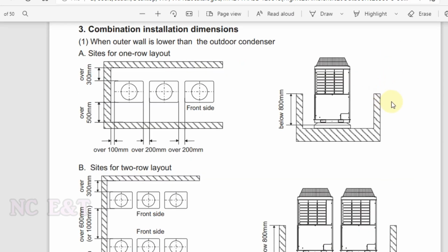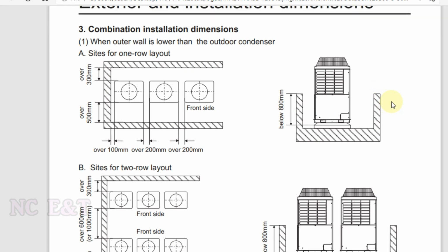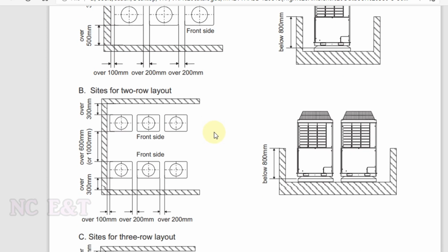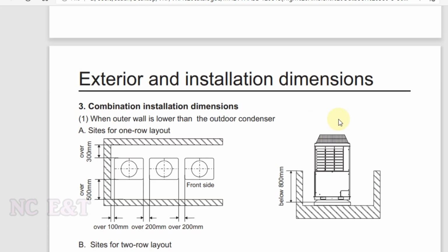There are some important points to be considered during the installation. If the location for the outdoor unit is covered by a boundary, then we must have a minimum clearance of 30 centimeter between the unit and the boundary wall. And if we have two rows of outdoor units, there must be a clearance of 60 centimeter between the two units. And the height of the boundary wall should not be more than 80 centimeter. If we have more height for the boundary wall, we must provide louvers to provide fresh air for the outdoor units.